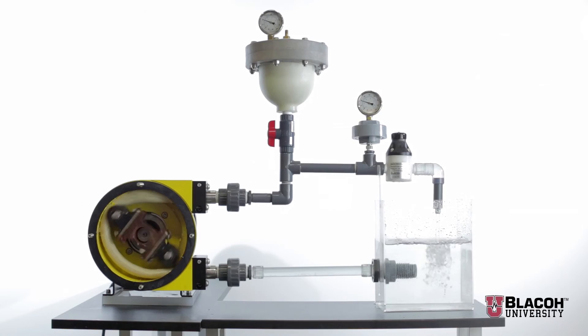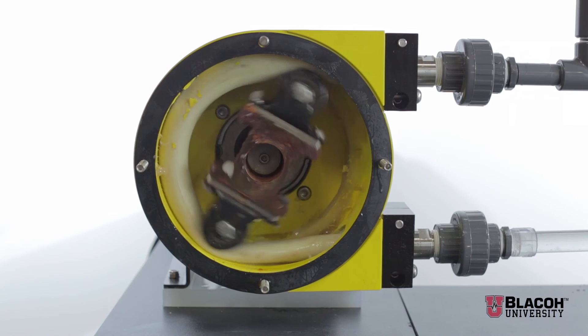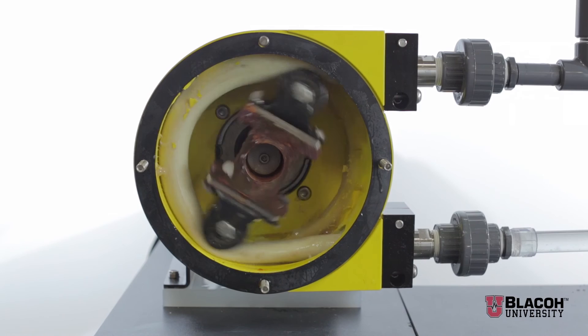If the pump inlet is under positive pressure, acceleration head will cause a pressure spike and vibration causing potential damage to pipe and components. If the pump inlet is under vacuum, cavitation and pump starvation can occur.